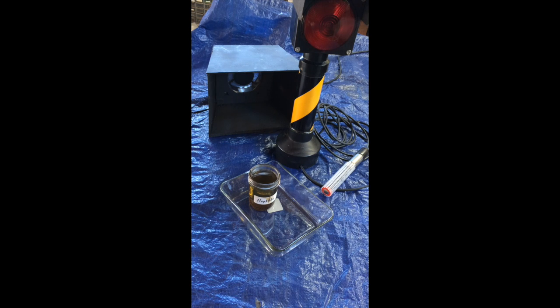Okay, it's now 11:18, November 6, 2015. The lab temperature is 62 degrees. And this is part 2 of a test of the TRM sensors SensorCom combination probe. As you can see, the flasher is still flashing. I've left it in the latched state after we did the brine detection test. This is fairly typical. The probe itself is probably reset at this stage, but the flashing indicator is designed to latch once it's detected the leak until you intervene.